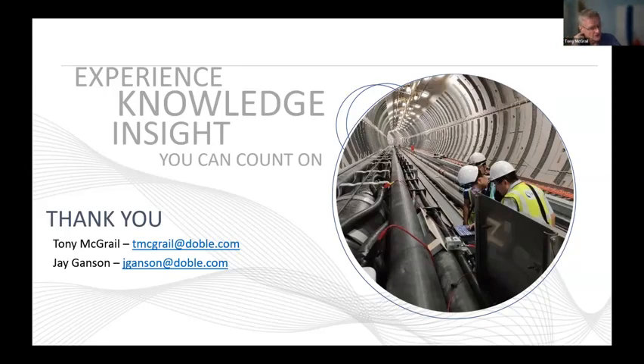When you apply it to power transformers, some people have found that it seems reasonable. When I was at Grid US, we did a very detailed analysis of transformer failures, and we found that after 60 years, we had not reached the far end of the bathtub. And it was very likely that by the time we got to that far end, we'd have no transformers left, just due to random failures in the middle stage of life. So you've got to be careful about applying bathtub curves, because they produce models of failure which expect a rise. Now, Chris earlier said in Memphis that that's what he found.